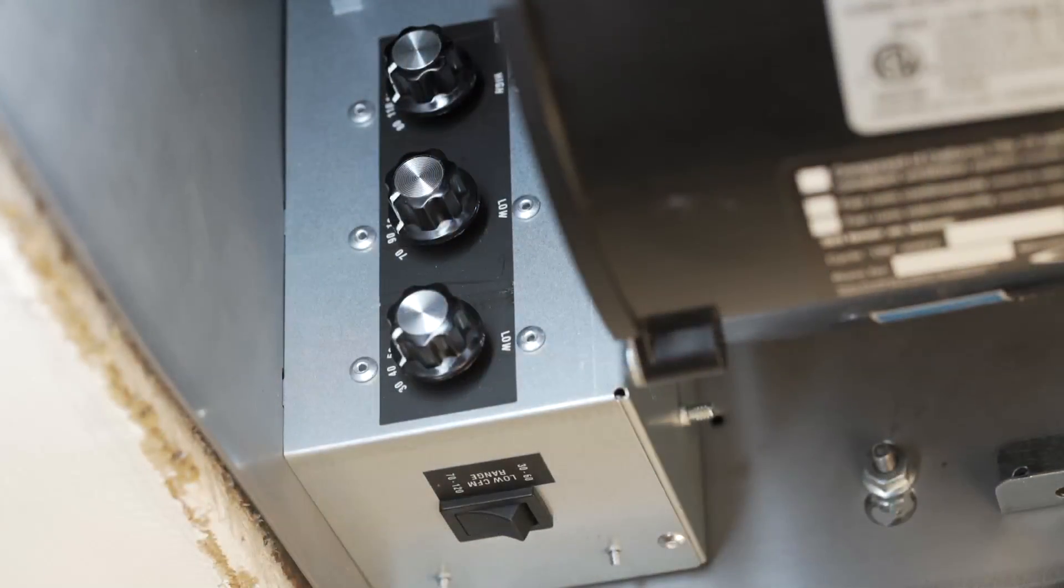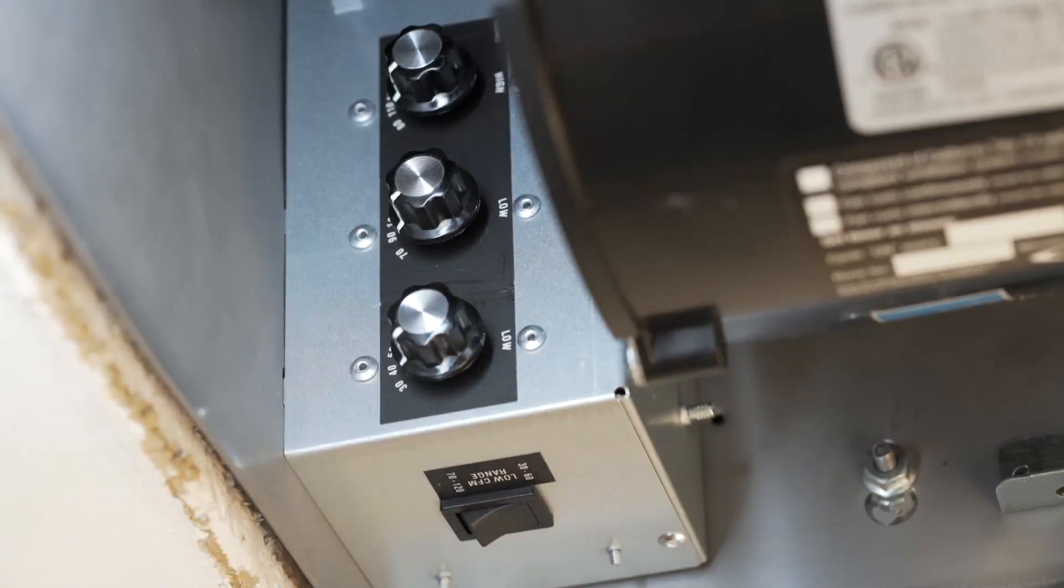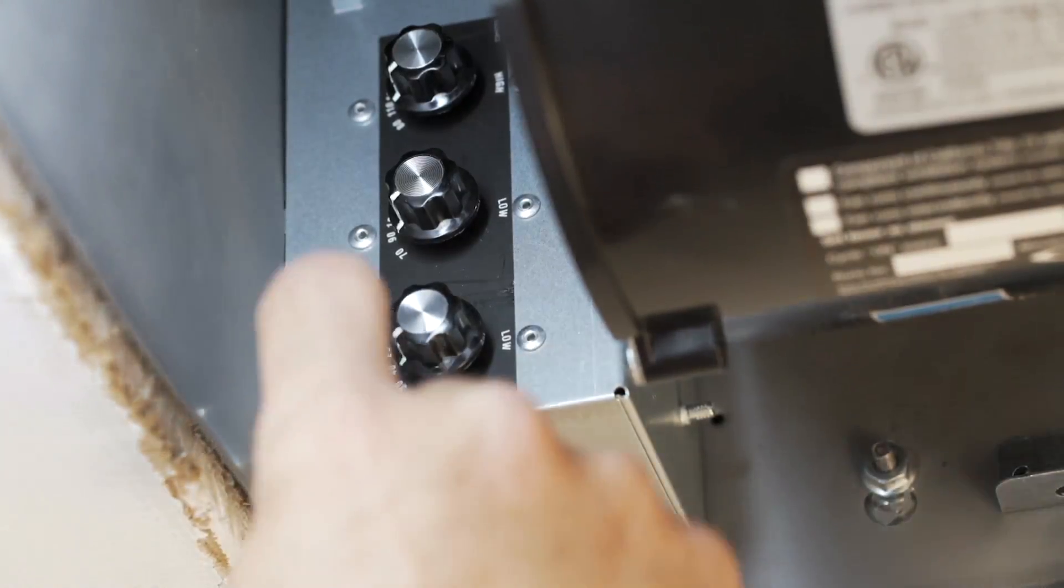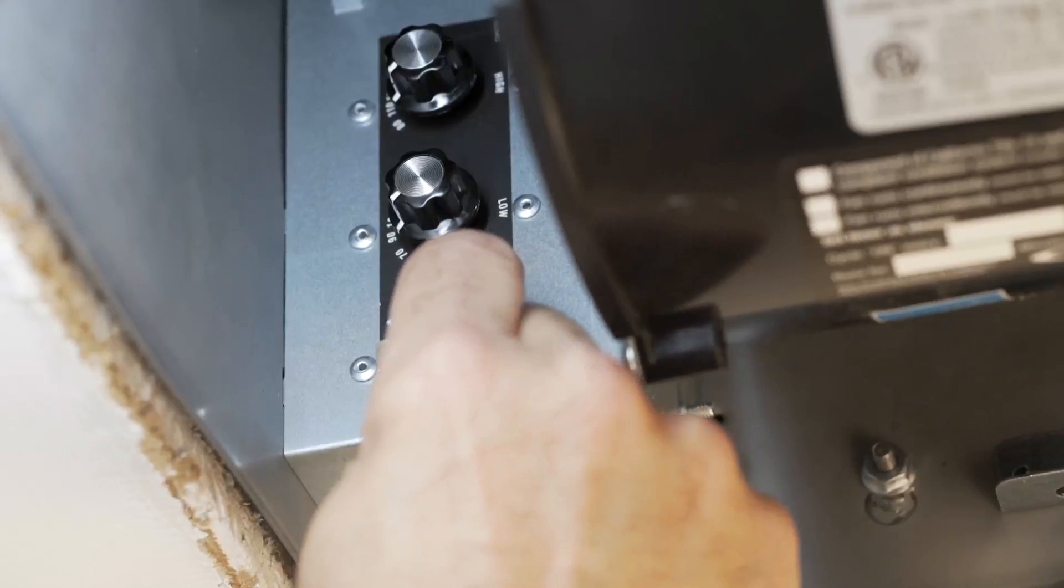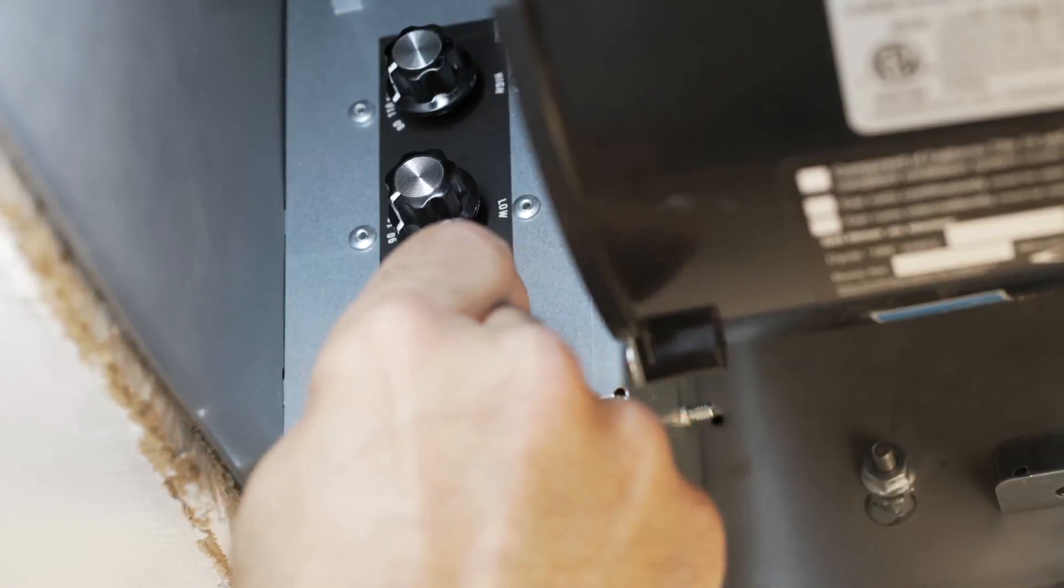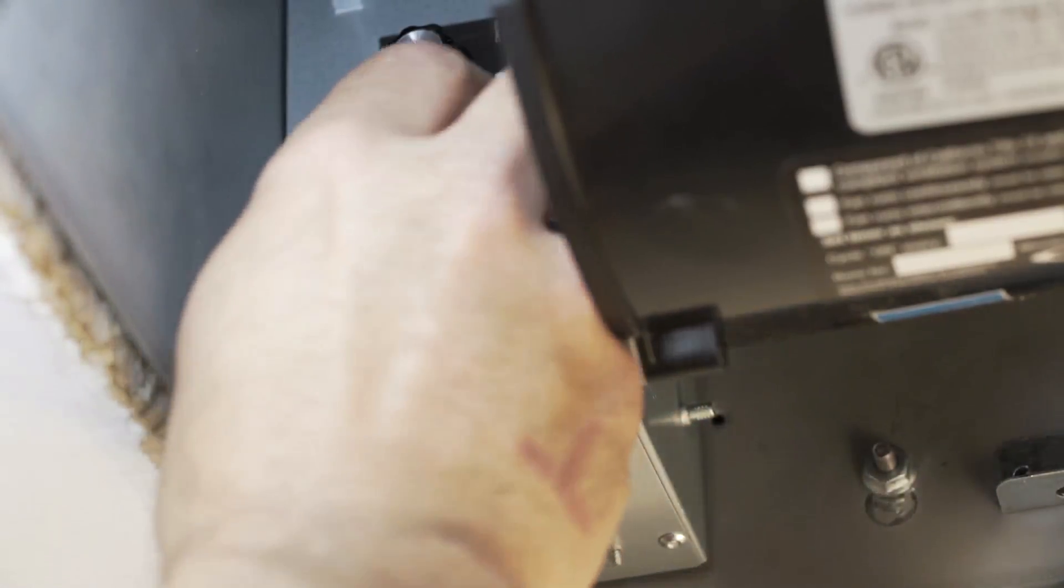To set the speed of the fan, first adjust the rocker switch to decide if you would need more or less than 65 CFM of ventilation. Once you have decided on the minimum required airflow, the fan CFM level can be adjusted by using the adjustment knobs as indicated in your instruction manual.